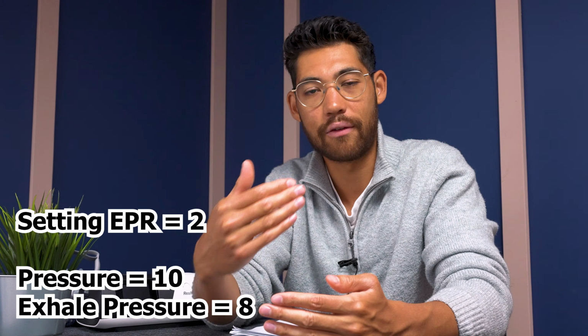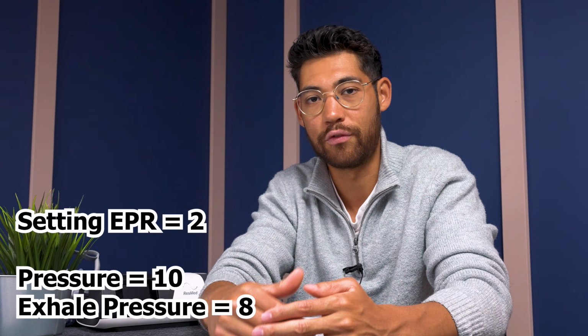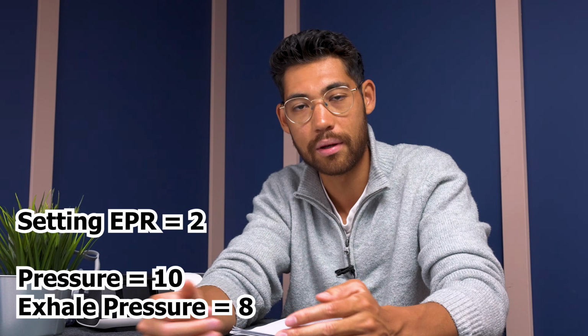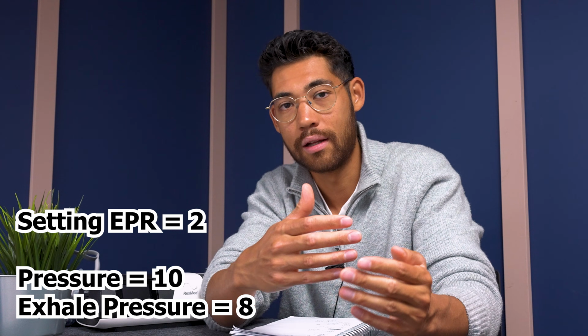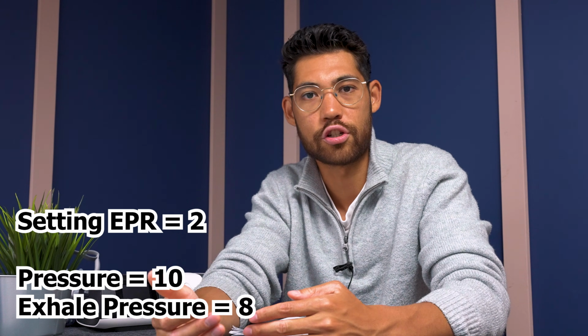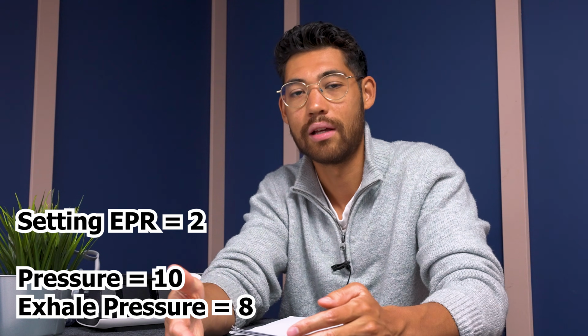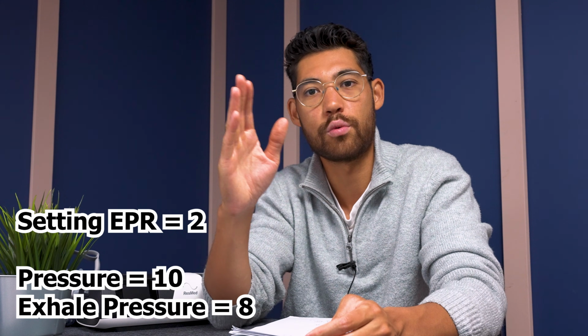So EPR is your expiratory pressure relief. It decreases the pressure with every exhale, similar to a BiPAP. So if your pressure is a 10 on CPAP and you have a 2 on your EPR, then your exhale pressure is going to be an 8, because 10 minus 2 equals 8. And that's going to fluctuate the pressures.